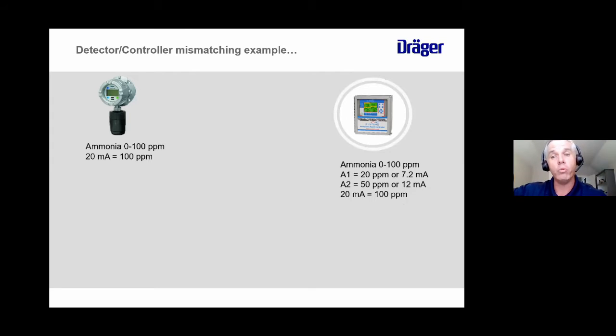You set your alarm at A1 of 20 ppm and an A2 of 50 ppm. At A1 20 ppm, what the controller is actually seeing is the transmitter sending out 7.2 milliamps, which is the value that 20 ppm corresponds to when you range 100 ppm. You set your A2 at 50 ppm, which is basically 12 milliamps coming out of the transmitter. So everything's all hunky-dory, everything's great.